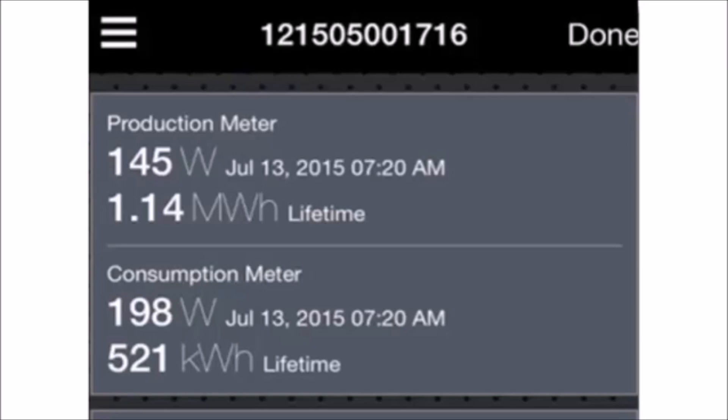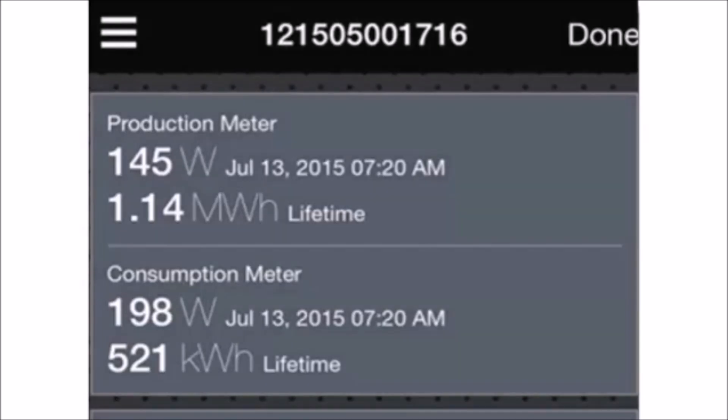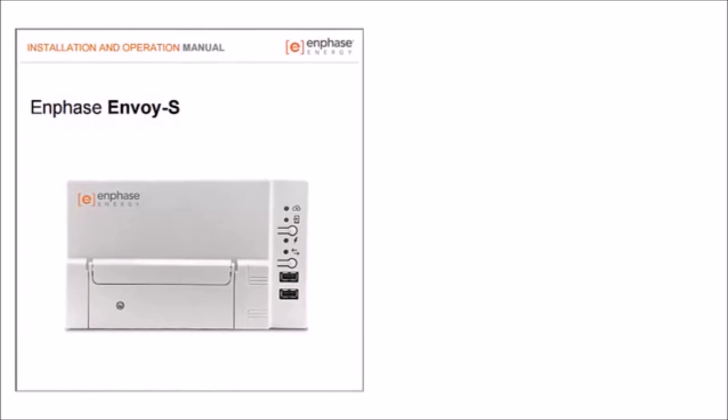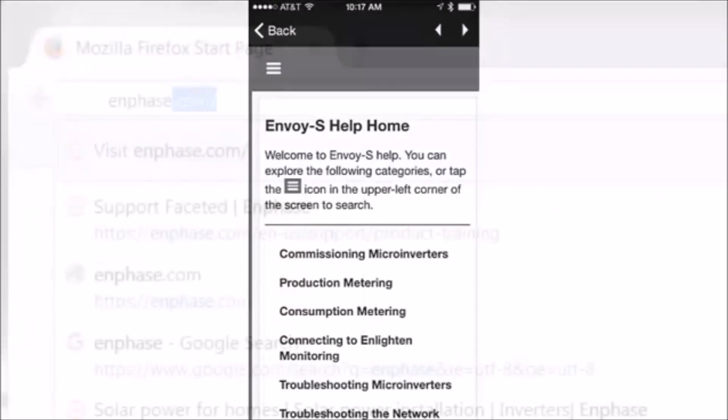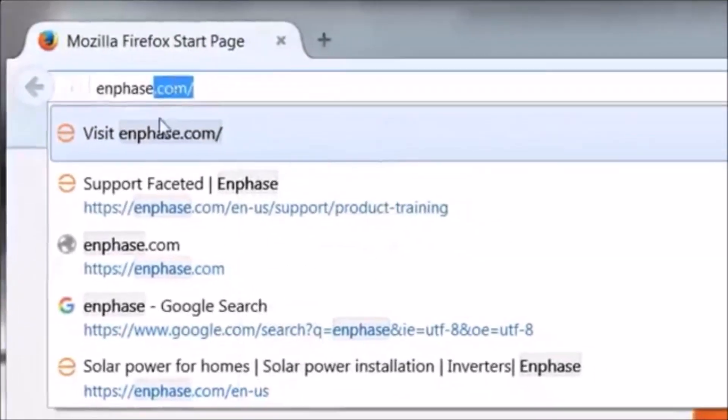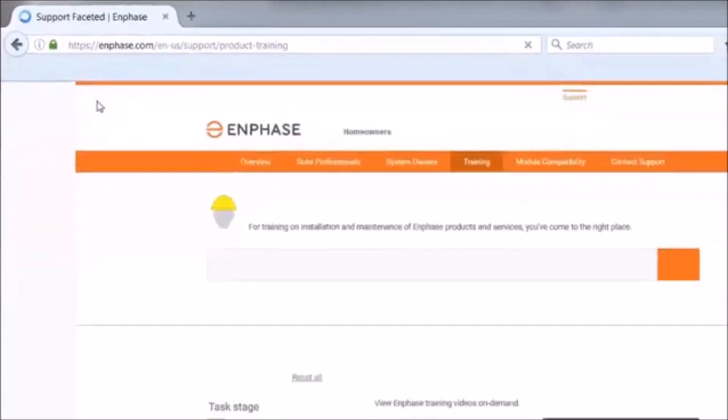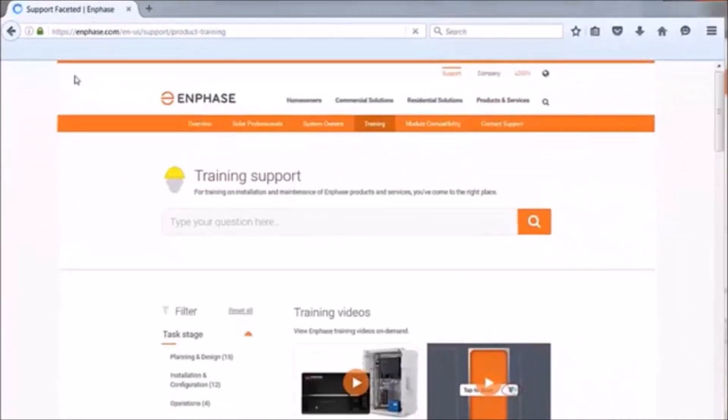If the consumption monitoring isn't working properly, a good first step is to shut off solar and validate the consumption metering without the PV producing power. For additional setup and troubleshooting information, please reference the Envoy S Installation and Operation Manual on Enphase.com, as well as Envoy Help when you are connected to an Envoy with Installer Toolkit. For additional training videos, please go to Enphase.com. Thank you.